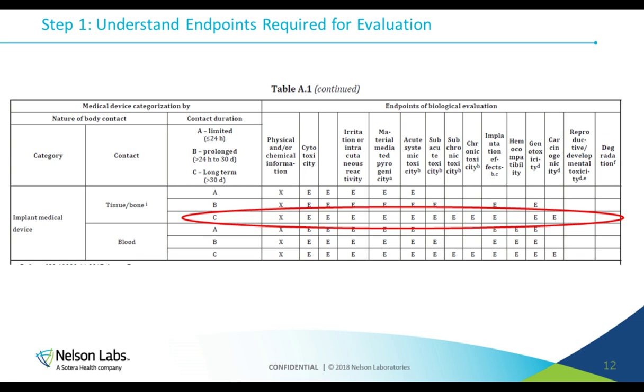So everywhere that there's an E, you have to have a section or a line in your biological evaluation report where you say, okay, cytotoxicity was required, we addressed this through testing, here was the result. Or it could say something like implantation is required, we know that 316L stainless steel doesn't represent a hazard from an implantation perspective, and the surface finish of the steel was per this ASTM standard, which has been tested a lot. Therefore, we didn't test it, we evaluated it, and it's not a hazard.